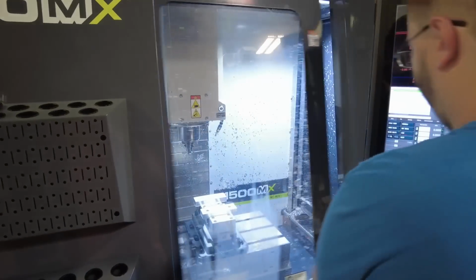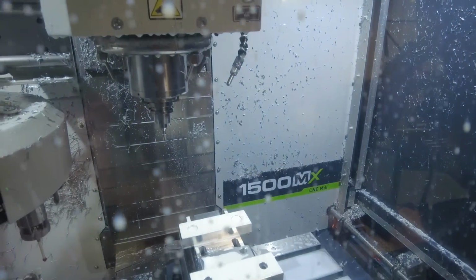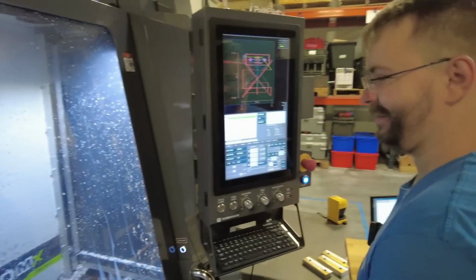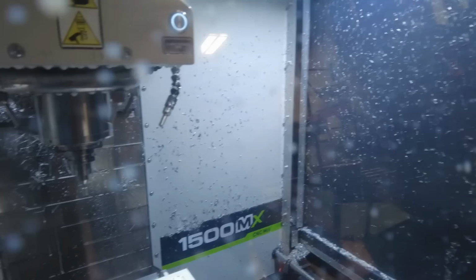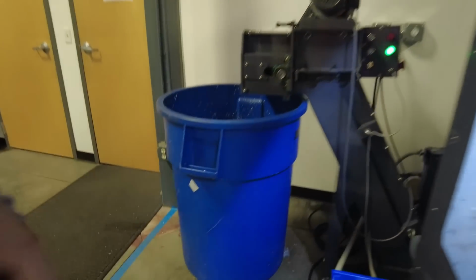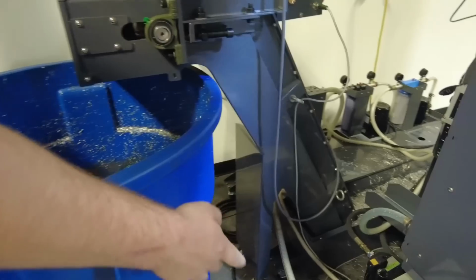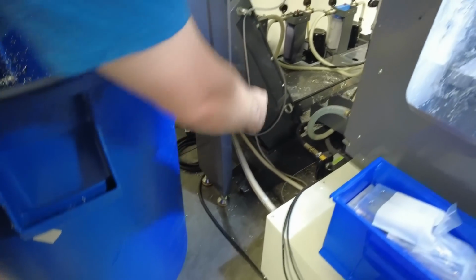So you're about to try to run coolant through the calibration tool? Yep, don't tell my boss, or the metrology nerds. Oh, that's running right now. Nothing exploded, and you can't even see it, but our pump's running, and we're going back through that bypass valve back there.